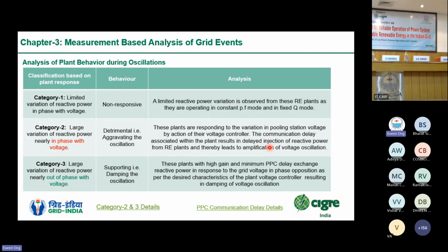The category 2 power plants were those in which large variation of reactive power could be seen, but these variations were totally in phase with the voltage. So when there is a rise in voltage, the injection from the RE plants is in phase with the voltage, and thus voltages are getting again amplified. So these were not helping the voltages to smoothen, to stabilize. Rather, they were causing the oscillations. They were leading to the amplification of the oscillations.